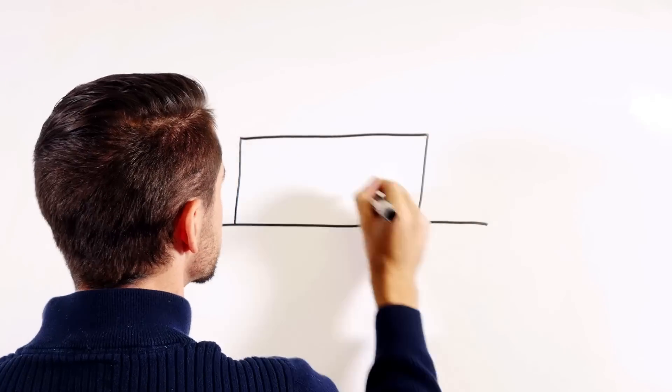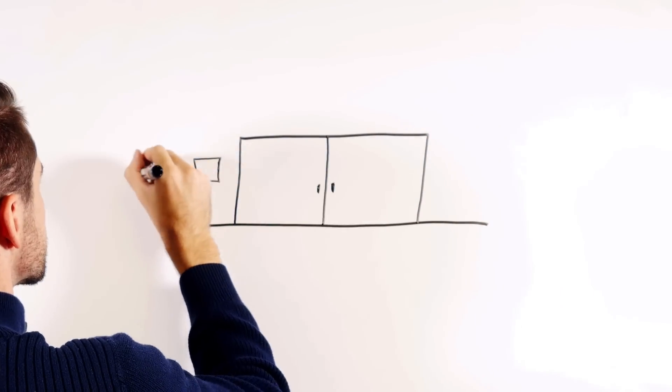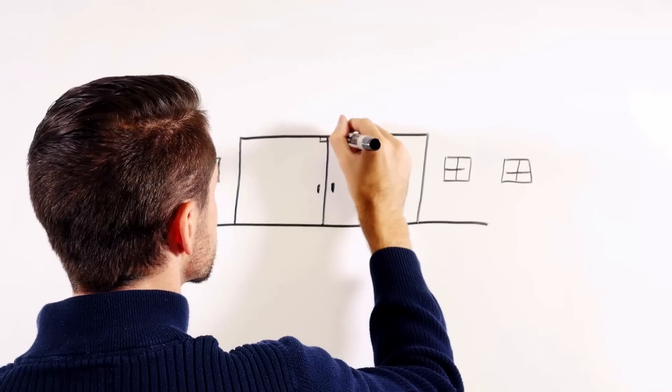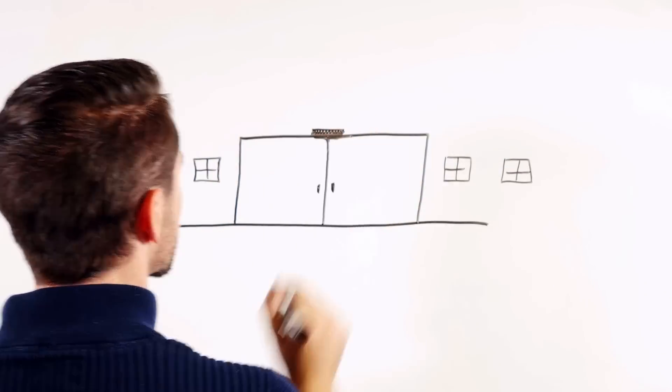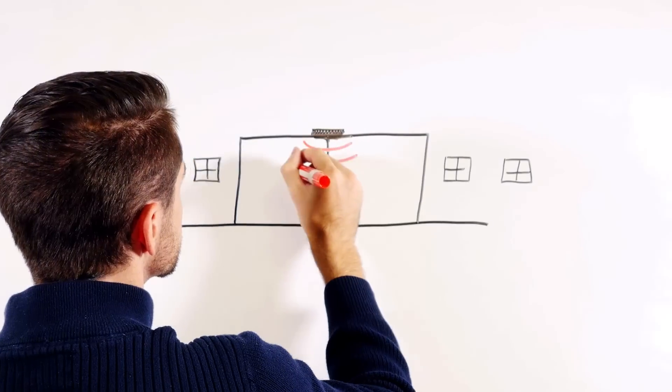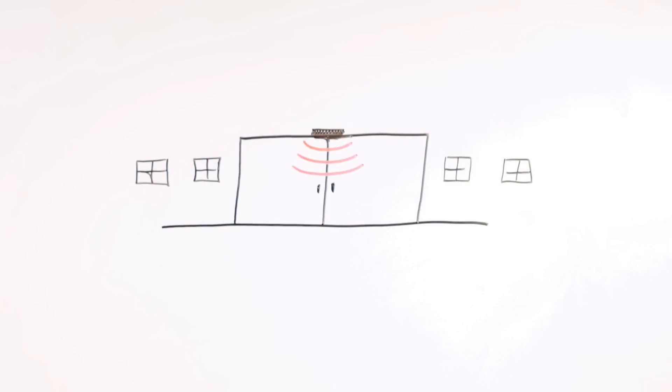This knowing act requirement, however, means the use of a motion sensor, once commonly used with low-energy automatic operators, does not meet the current standard. If a motion sensor is used with a low-energy automatic operator, the operator must comply with the safety standards defined by the high-energy standard, ANSI BHMA A156.10.